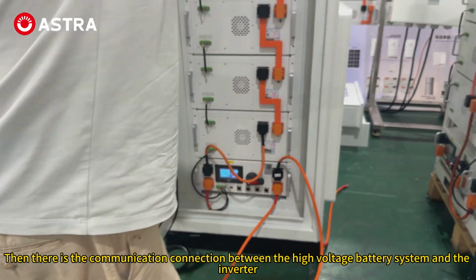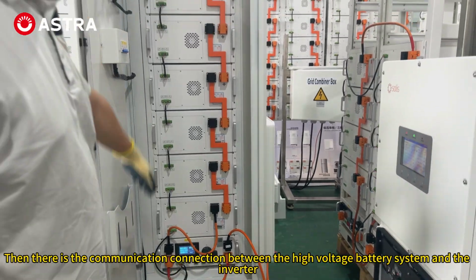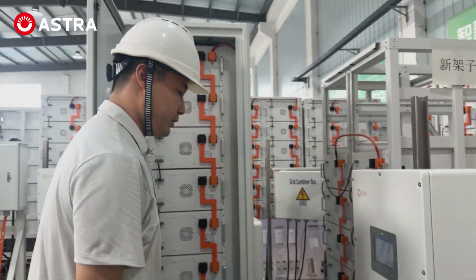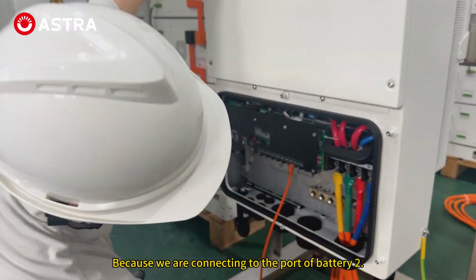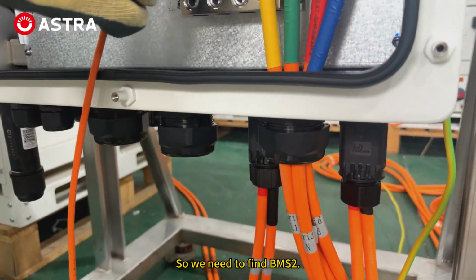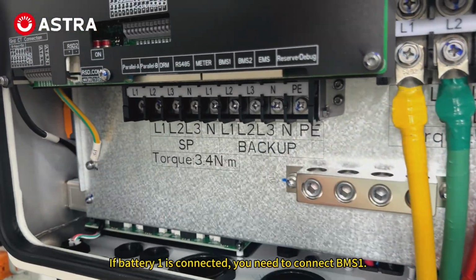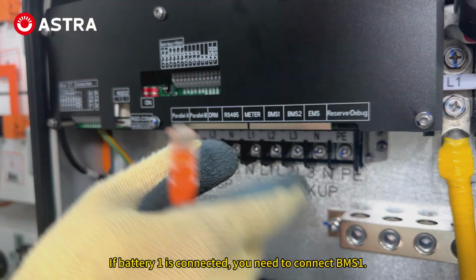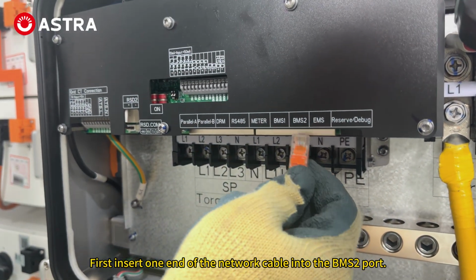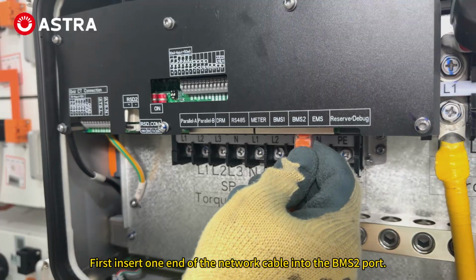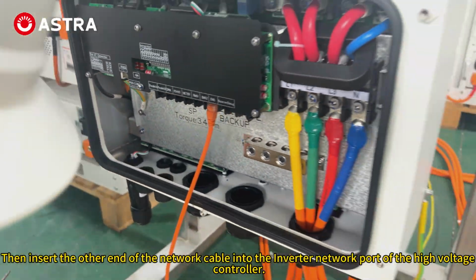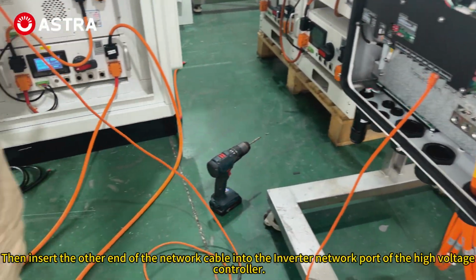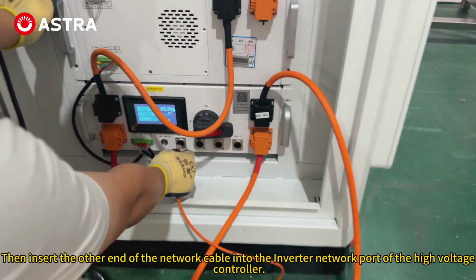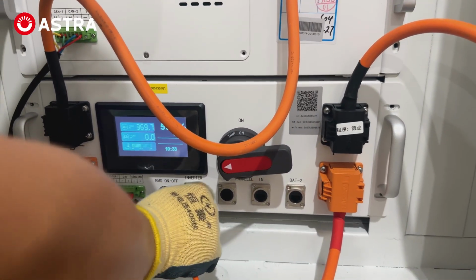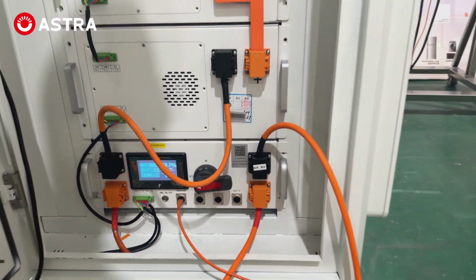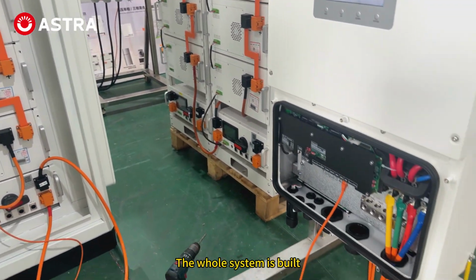Then there is the communication connection between the high voltage battery system and the inverter. Because we are connecting to the port of battery 2, so we need to find BMS 2. If battery 1 is connected, you need to connect BMS 1. First, insert one end of the network cable into the BMS 2 port. Then insert the other end of the network cable into the inverter network port of the high voltage controller. The whole system is built.